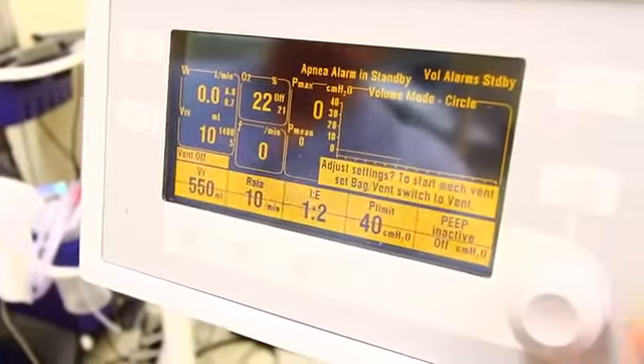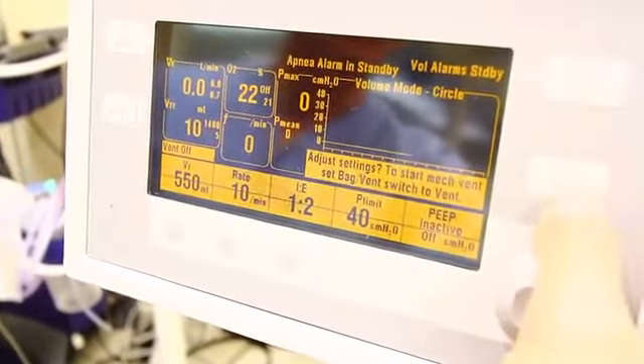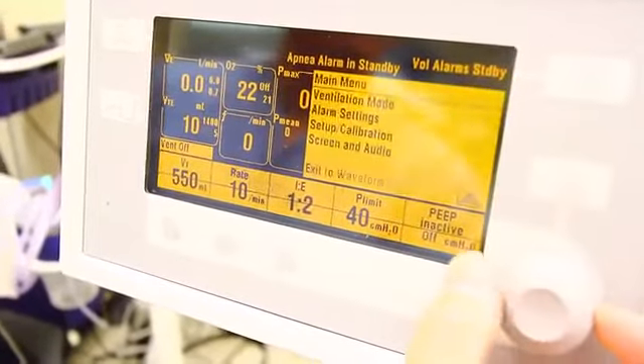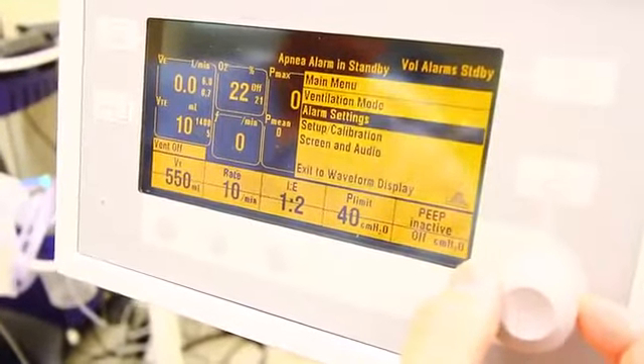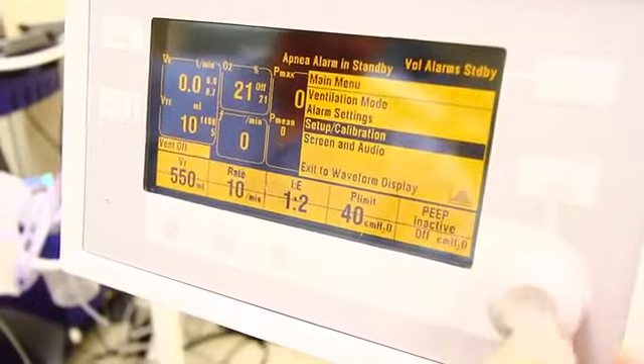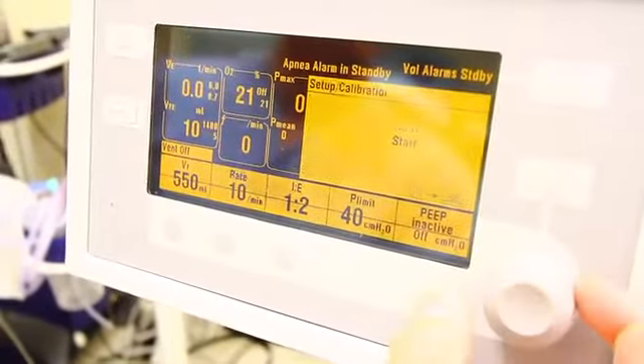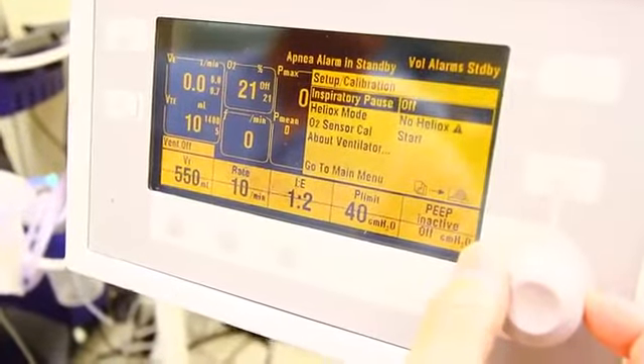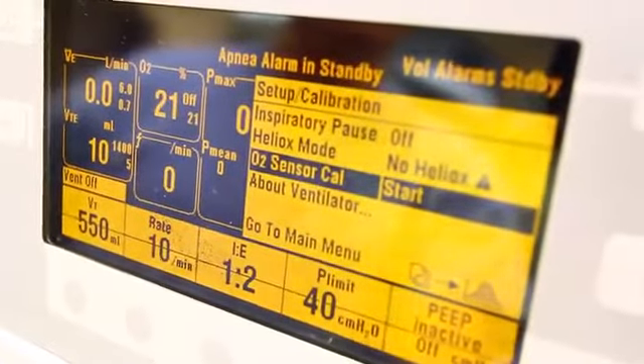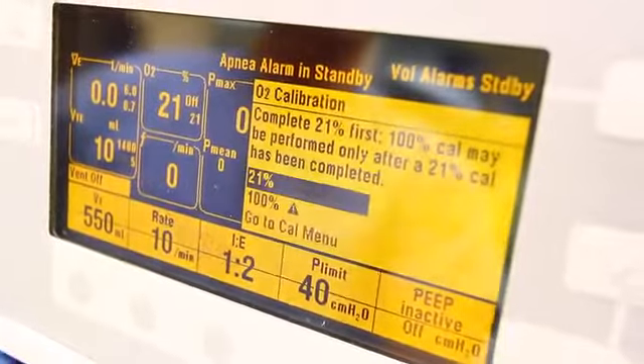In order to calibrate the oxygen sensor, you press the menu button, turn the knob counterclockwise until you can select Setup and Calibration, push the knob, again turn it counterclockwise till you get to Oxygen Sensor Cal, and then press the knob again to start.